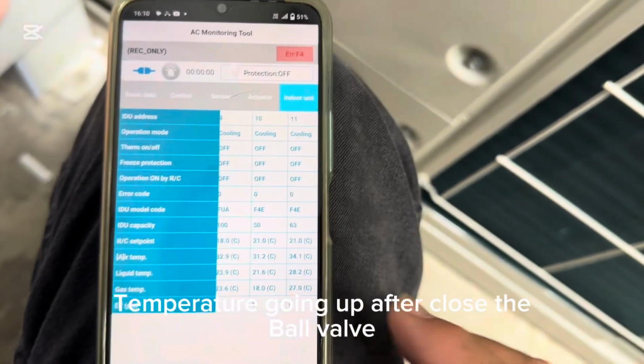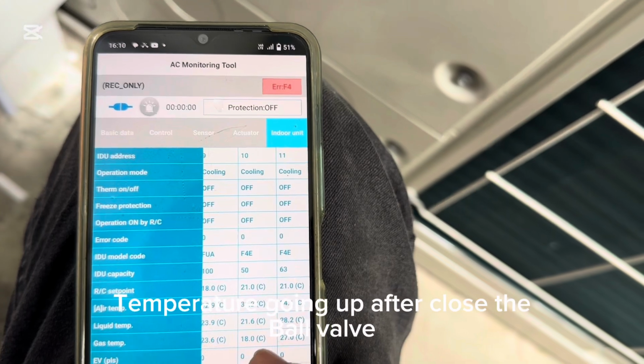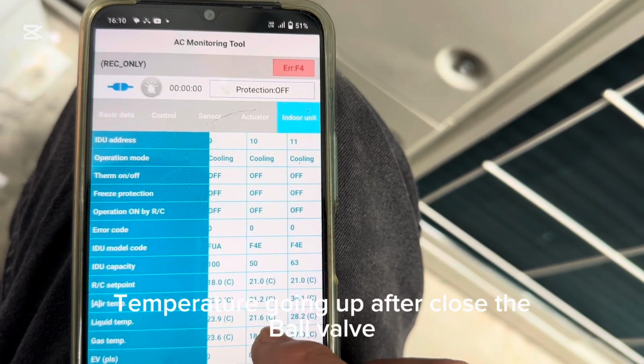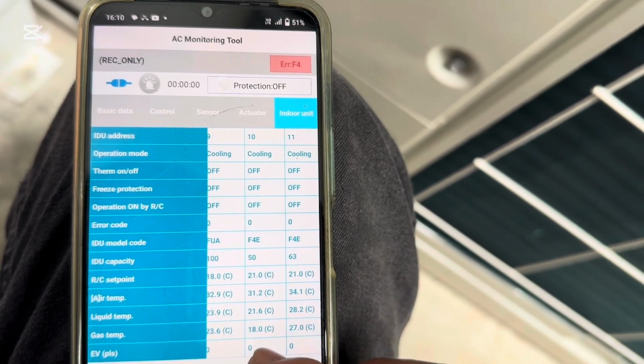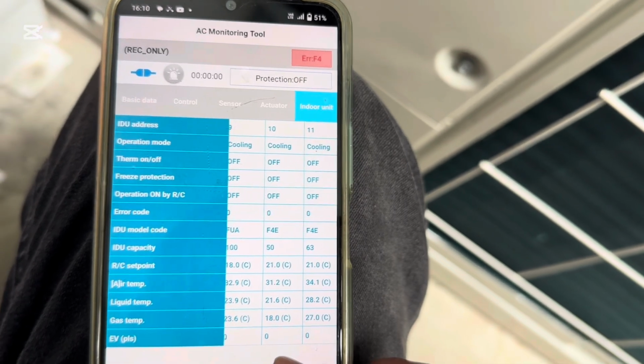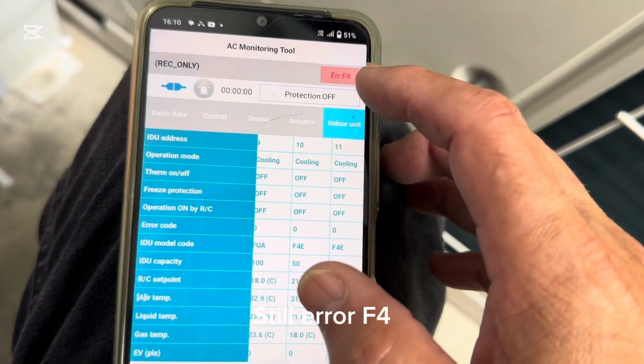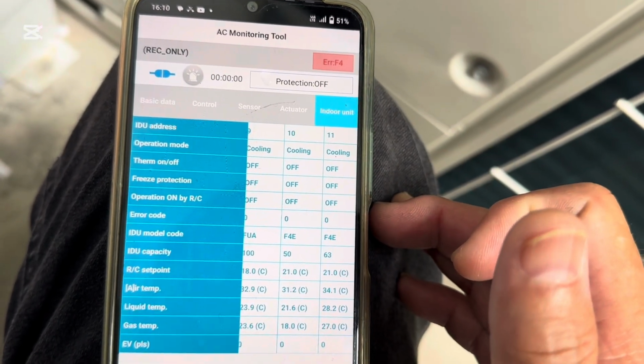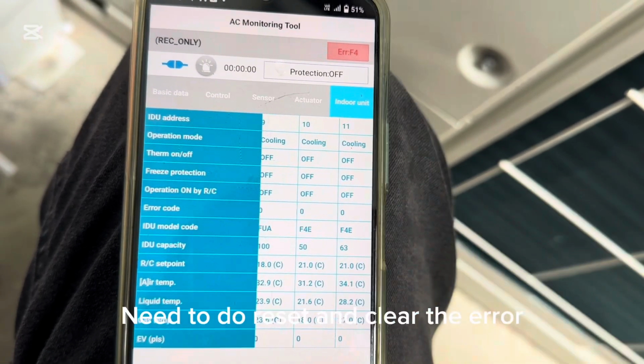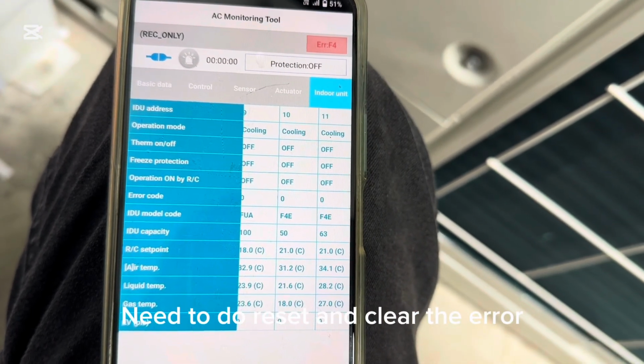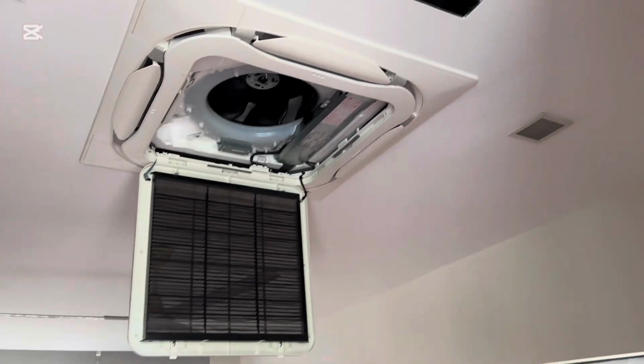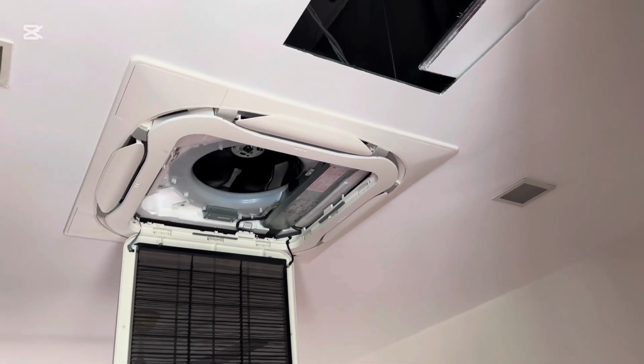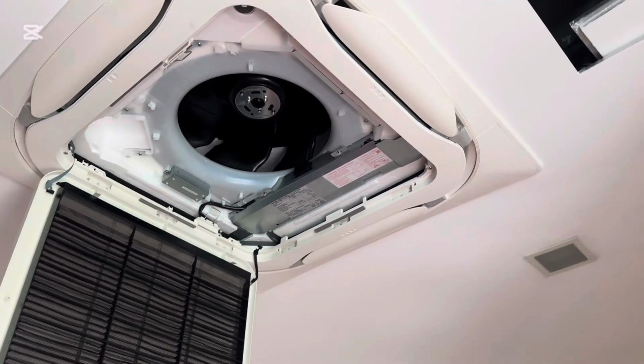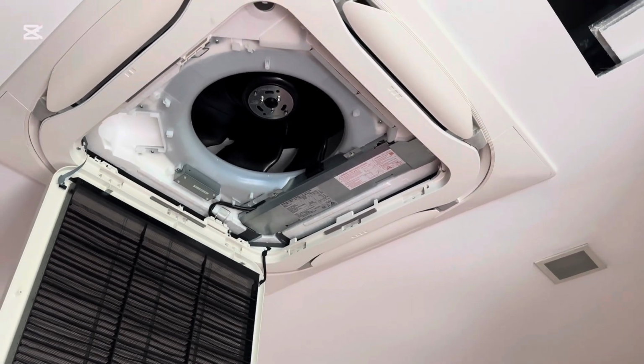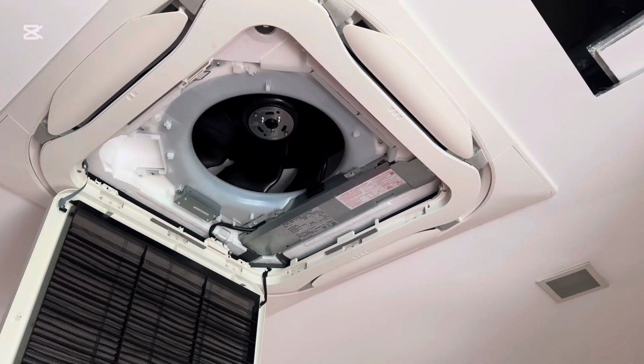Okay, after closing the ball valve, the temperature is going up. Liquid temperature 21.6, gas temperature 18. Okay, but still at F4. I need to do a reset and clear the error. So far the ball valve is very closed, the sound is no more, and I need to terminate this unit for temporary.